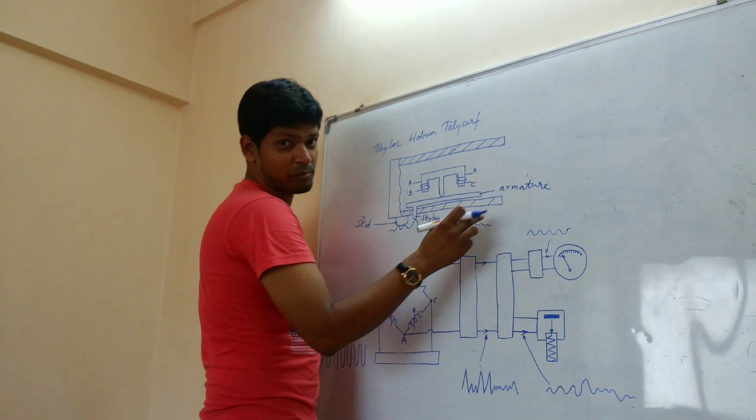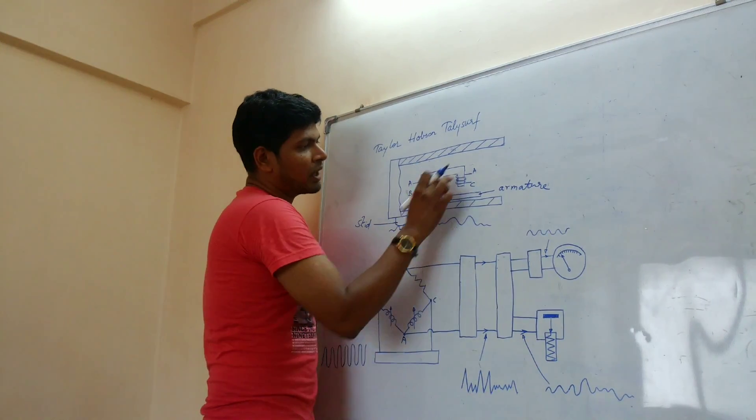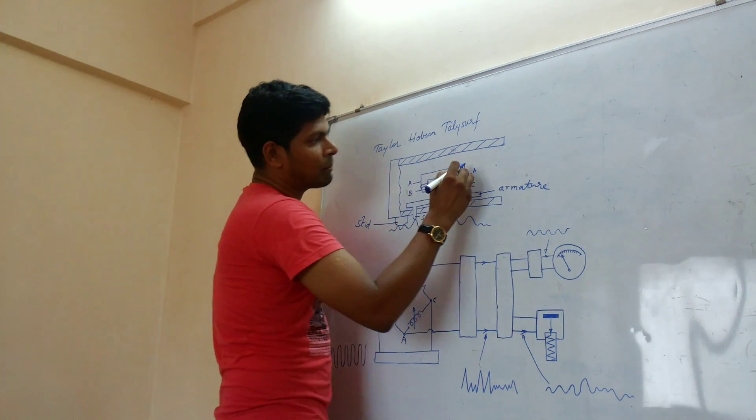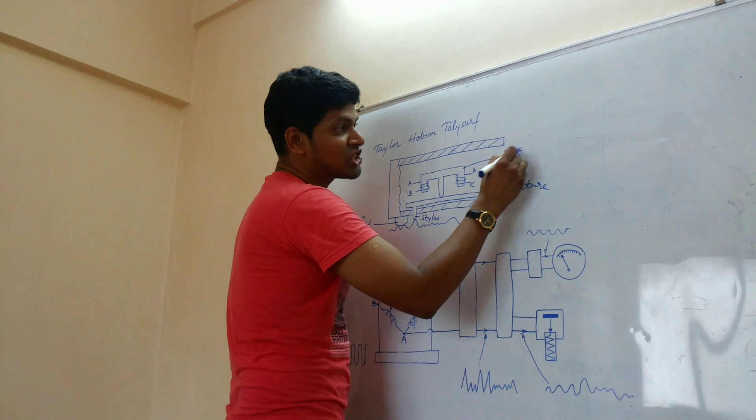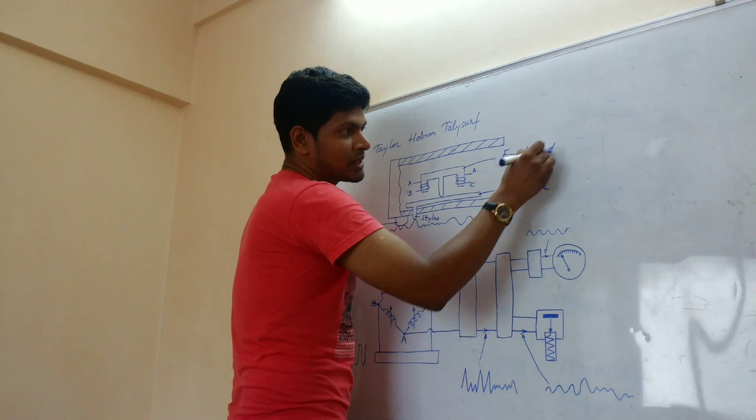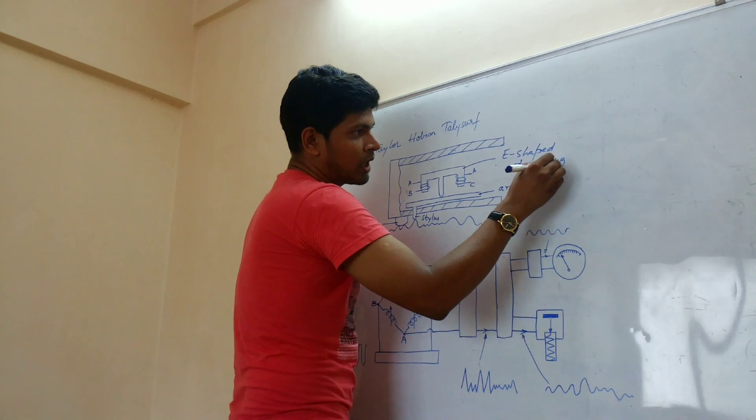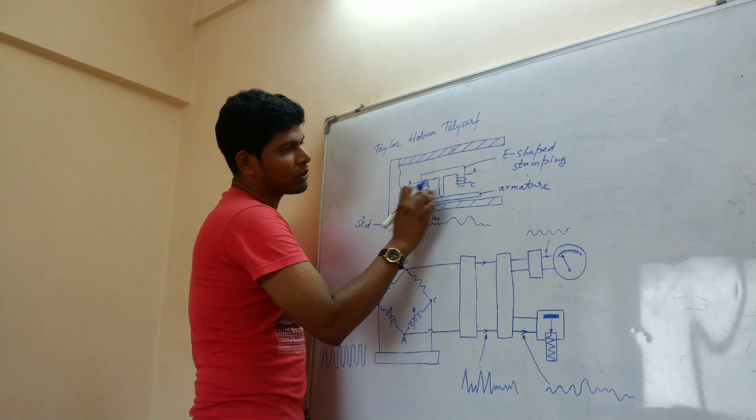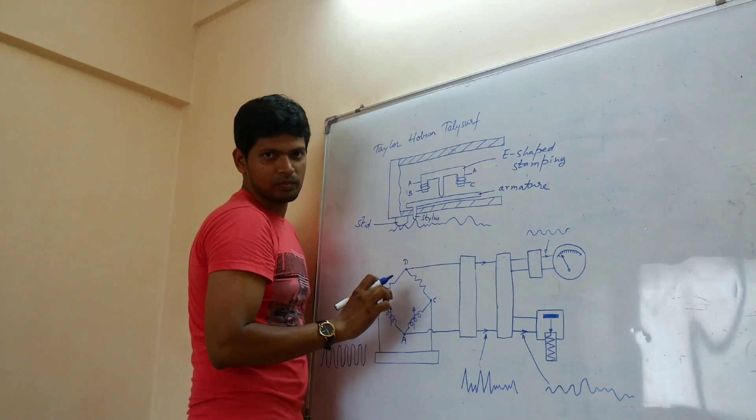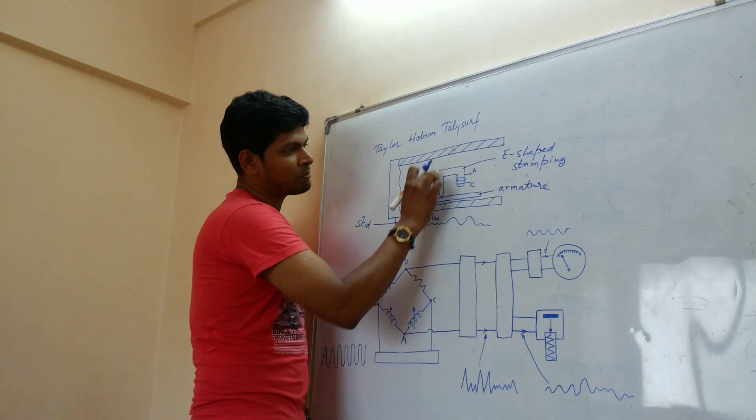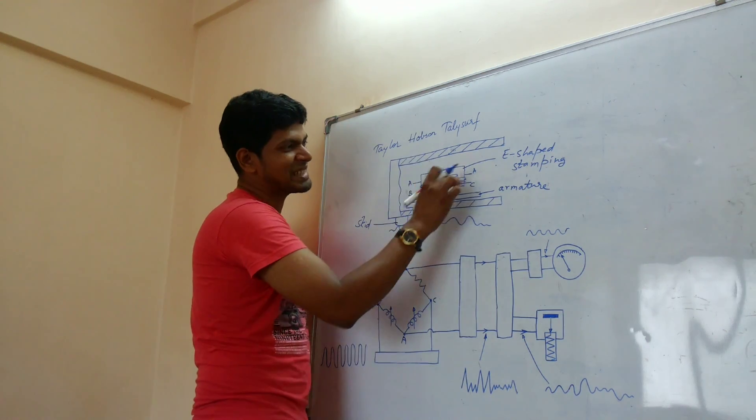And this armature is pivoted at the E-shaped stamping. This is E-shaped stamping. Here you can see there is an air gap and the armature is pivoted on the middle leg of the E-shaped stamping.